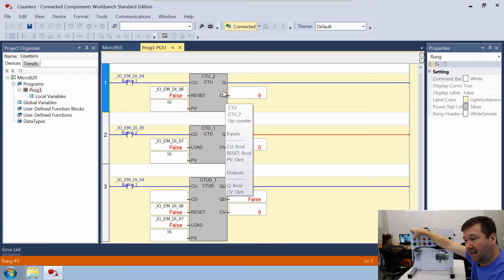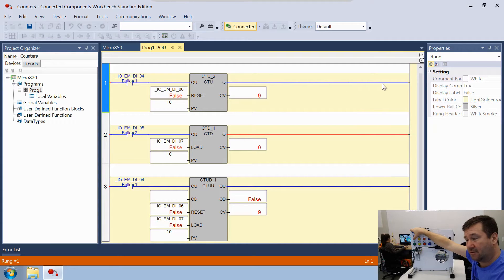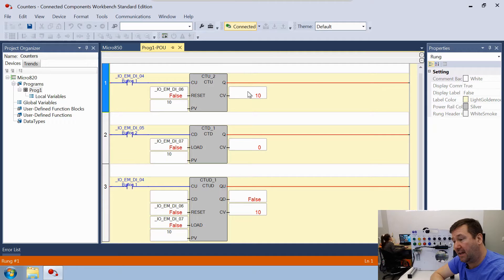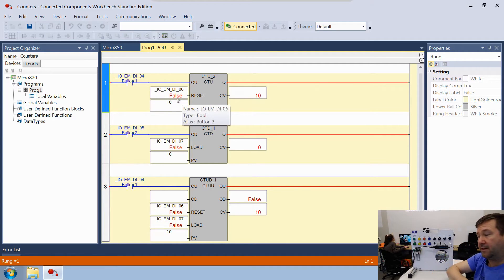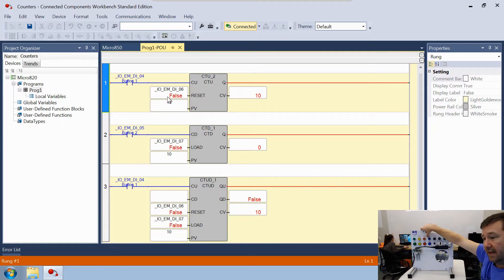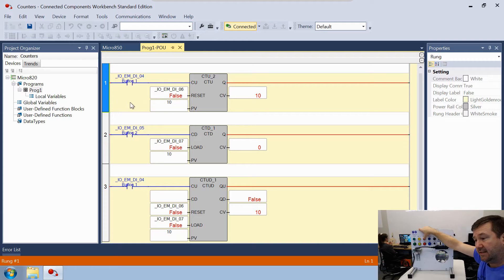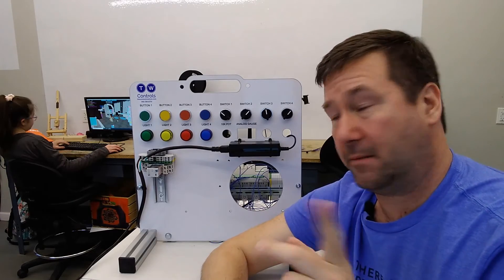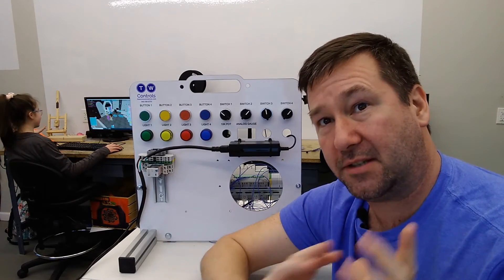Keep pressing up to 9, and on the tenth press you'll see the Q bit turn red, meaning it's true. The Q bit is true whenever the counter value is greater than or equal to the preset value. The Reset input is connected to Button 3 — press it and the counter zeroes out. That's the basics of the count-up counter.